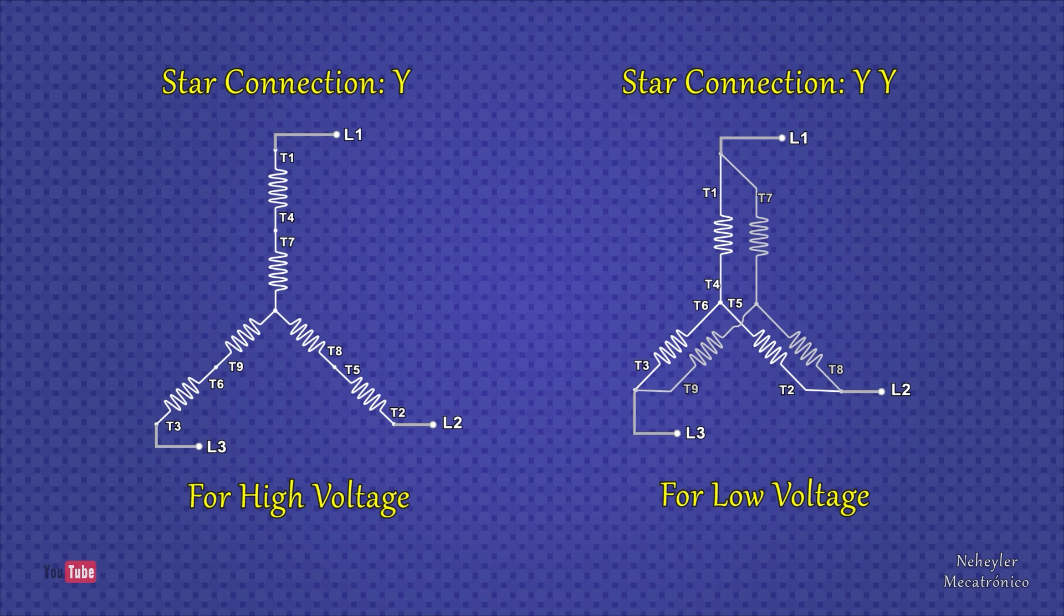If a motor is internally connected in star, then the connection can only be made in the terminal box in series star for a high voltage or in parallel star for a low voltage.